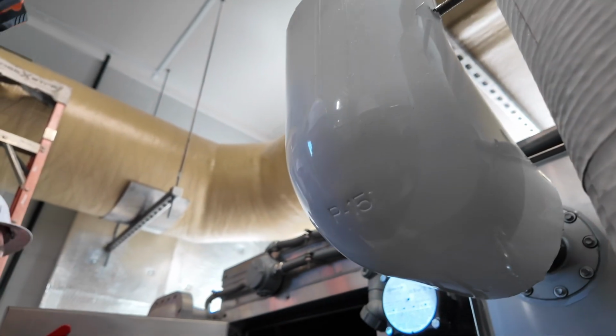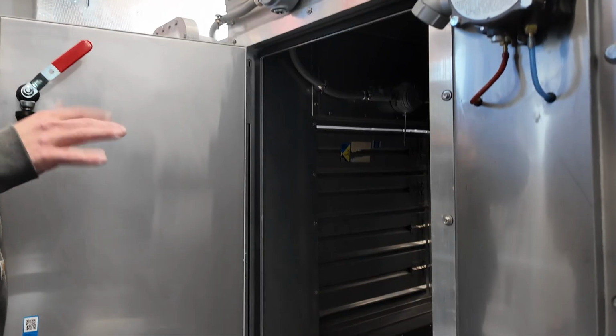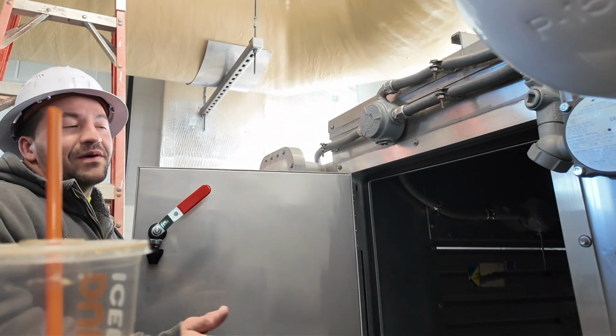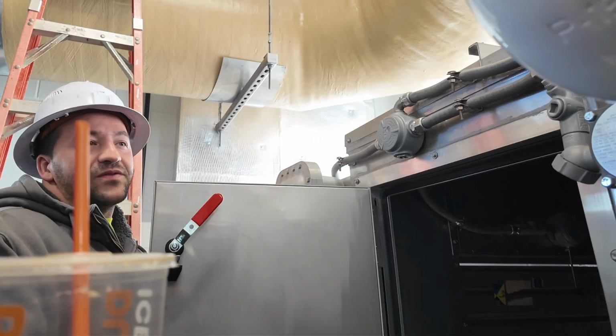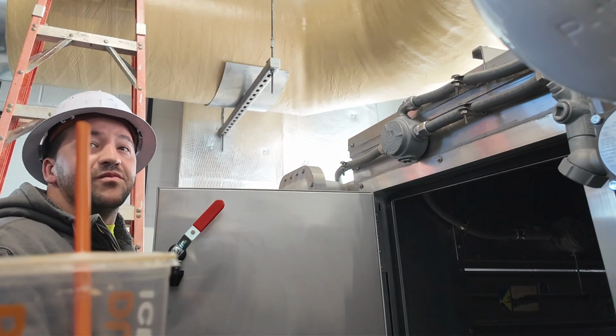How do you pop them out? You just kick off and then kick out the bottom. This is measuring the differential pressure across the filters. So if they're plugged solid, you'll get an alarm. With this being in the woods, with all the trees around it, you'll probably get a good amount of pollen buildup on them. So definitely during pollen season, you probably want to change them more often.